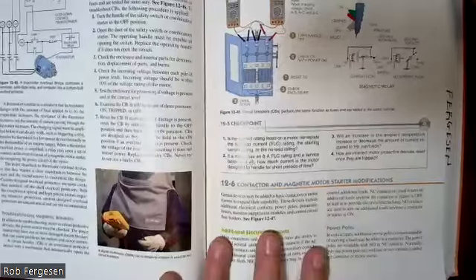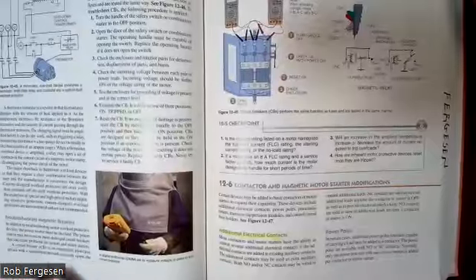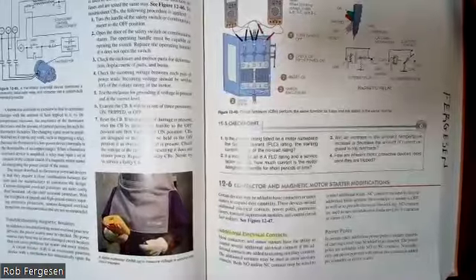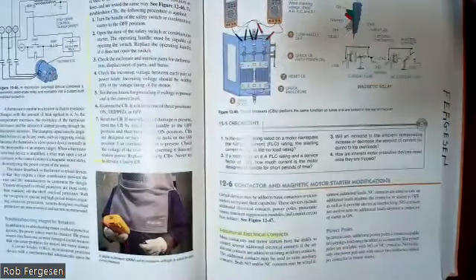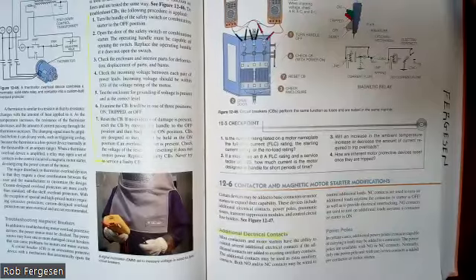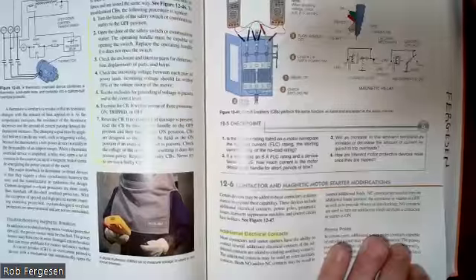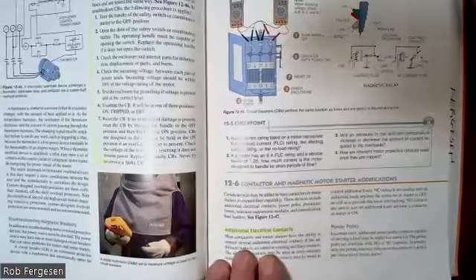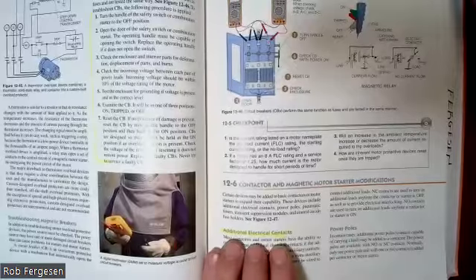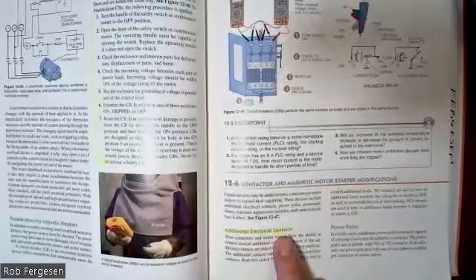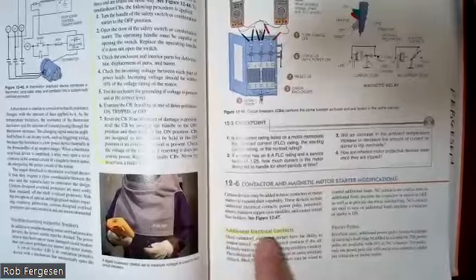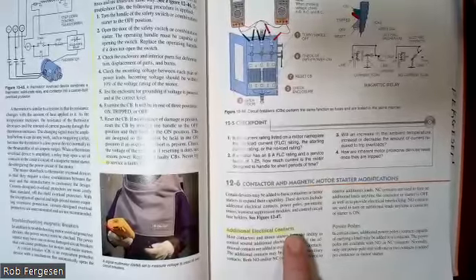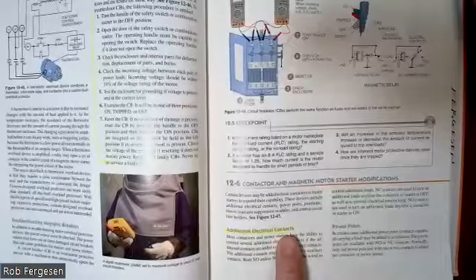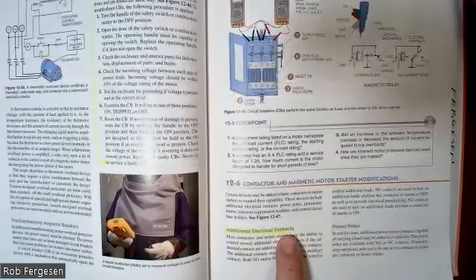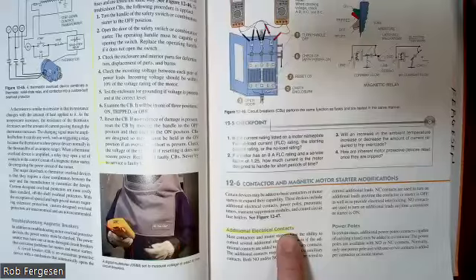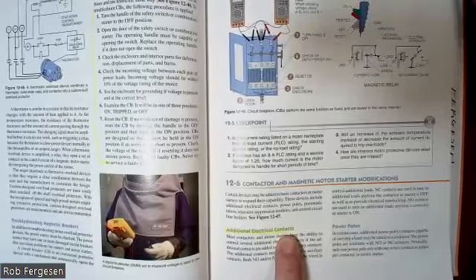Talks about different ones. All right, so let's get into the troubleshooting. Excellent troubleshooting guide. I can highlight that. Gives you some basic steps for troubleshooting your motor starter. And the final part of chapter 12 talks about what they call modifications. And the most important one for us, for our control circuits, are additional electrical contacts. A lot of times you're going to have in a motor starter a built-in auxiliary contact that you would use to latch in that motor and keep it running, instead of having to have a switch hold it down all the time. That way it's easier and quicker to stop with a stop push button. And you can build safety circuits in better that way.